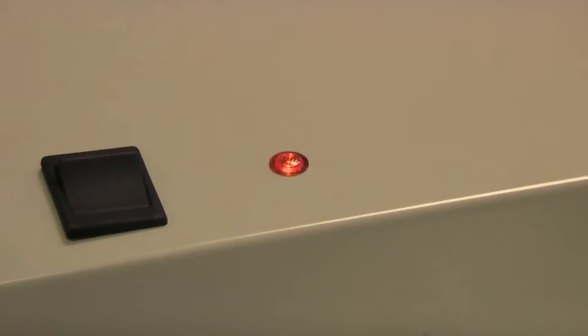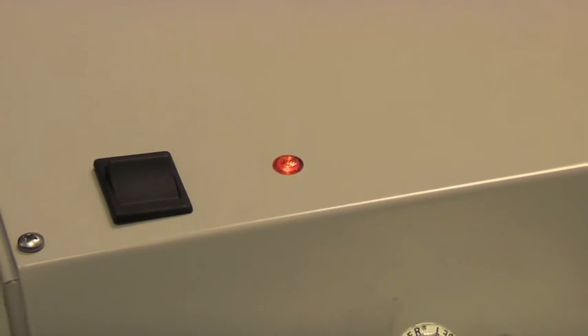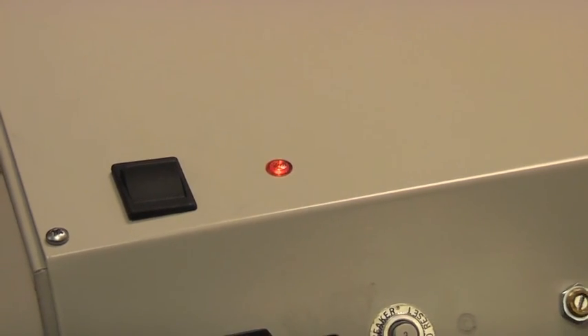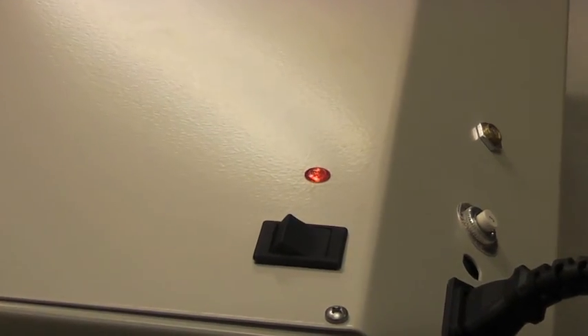A red filter alarm light illuminates to alert the operator to low airflow conditions that may indicate a loaded pre-filter or HEPA filter.